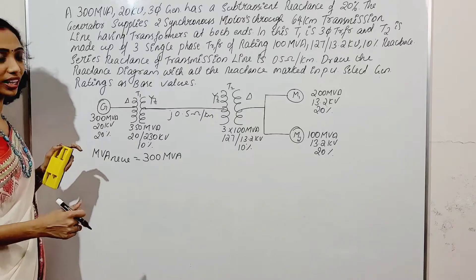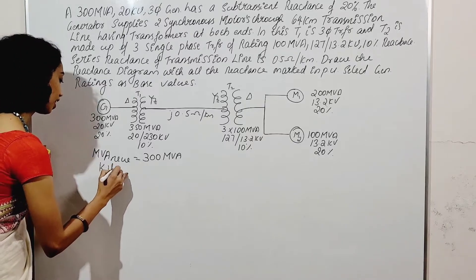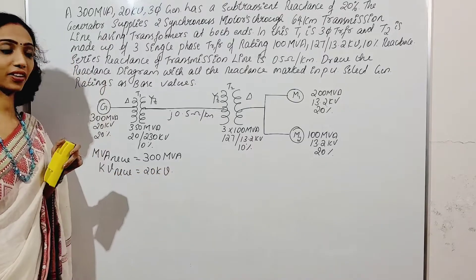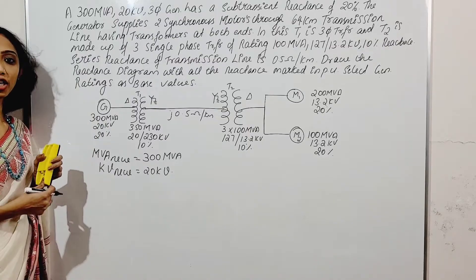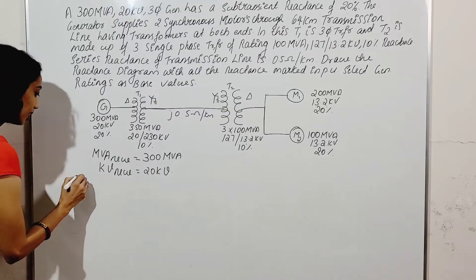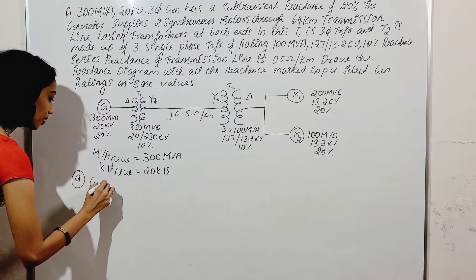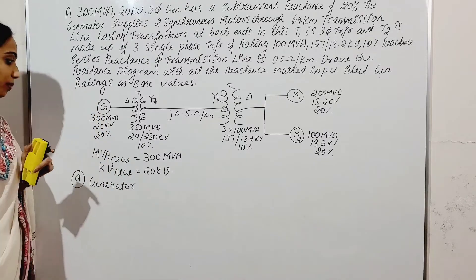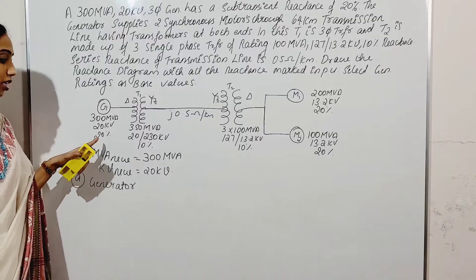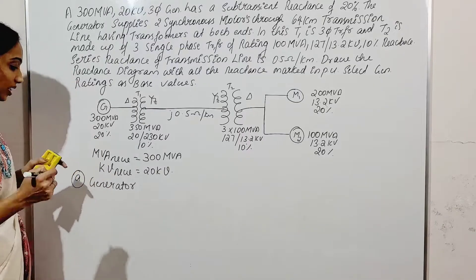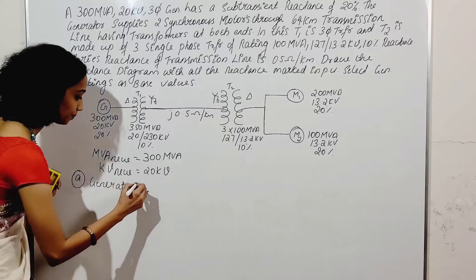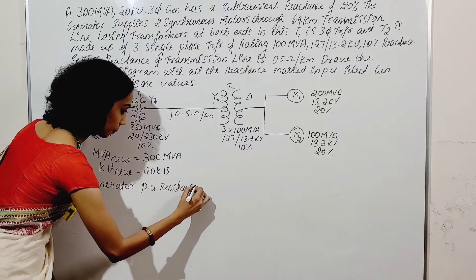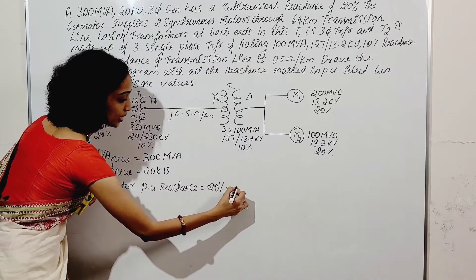MVA new is equal to 300 and KV new is equal to 20 kV. That means the generator per unit reactance — first we write the name: generator per unit reactance. Our base values are the generator values. Per unit reactance of the generator is 20%, which is equal to 0.2.